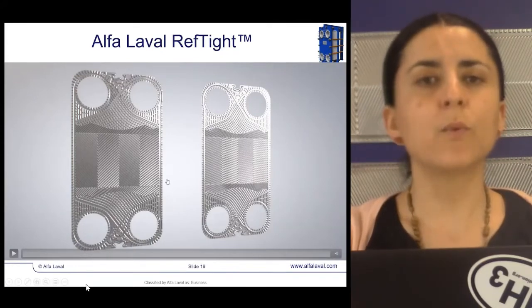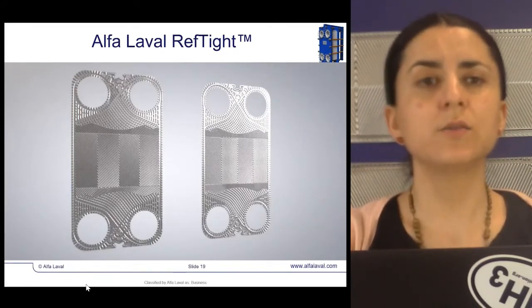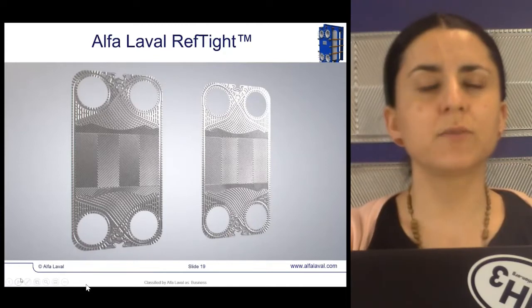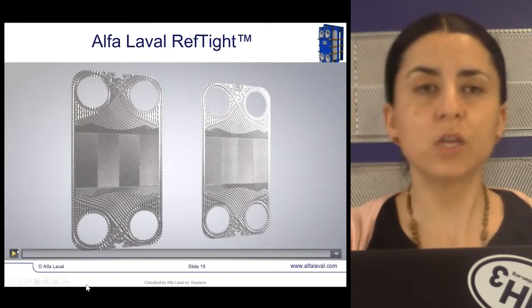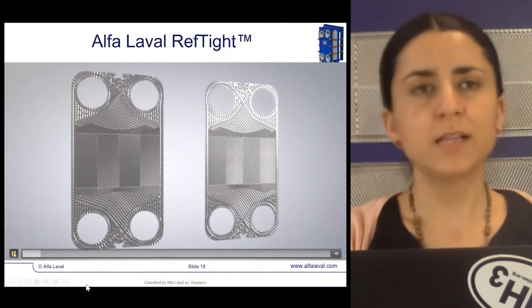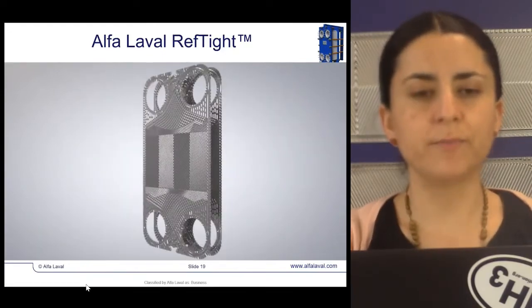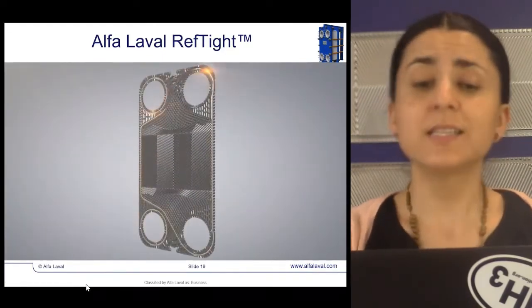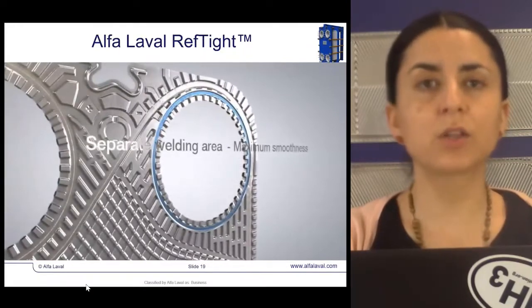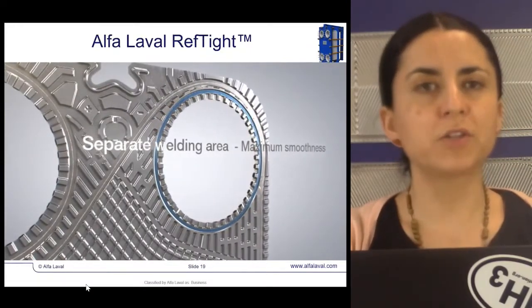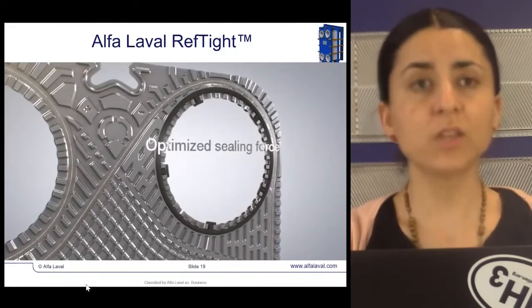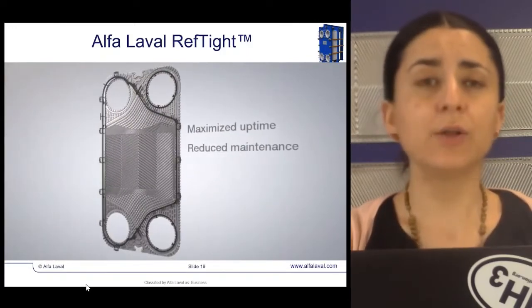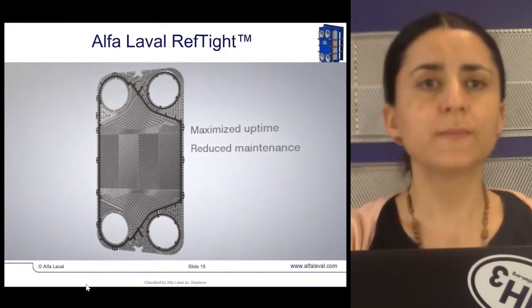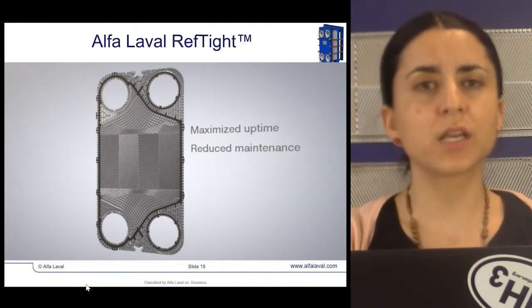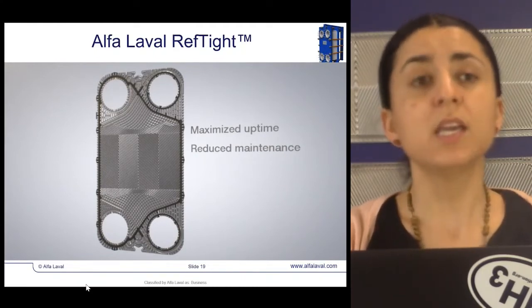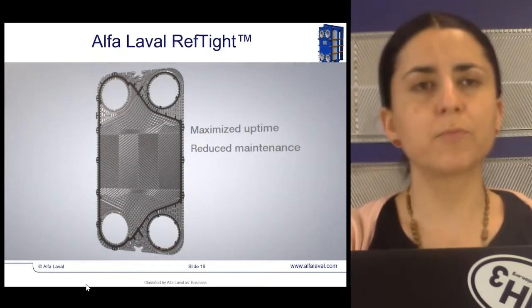These features are what define the next generation of gasketed plate and frame heat exchangers, and they are unique to Alfa Laval. Let's talk briefly about 3 of them. Omega port, for instance, is a sealing system that enables long-term performance for high pressure and high temperature.